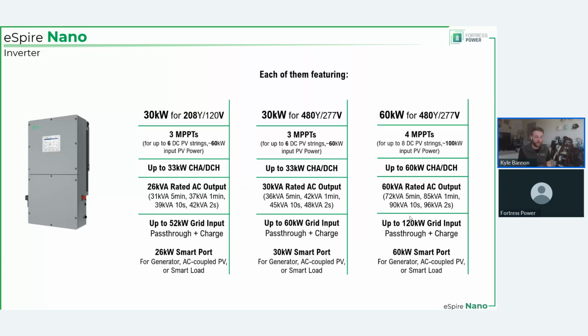And then I mentioned the smart port. That smart load port setting is going to be used for either a generator, AC coupled PV, or that smart load. It's the same port that's going in. So just know you can only use one at a time. You can't do both AC coupled and generator. It's or. Now, there are other ways to set it up to coordinate these things, but if you're going to use a smart port, you have to select one of those.